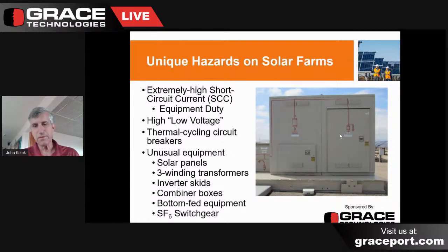And of course, solar farms are usually in a desert, someplace where you have a lot of sunshine, and the ambient temperature might be 120 degrees, and then you operate the system at full load plus a little bit more. You can imagine that it's extremely hot in there, and then it cools down at night. So this thermal cycling really puts a premium on maintenance, breaker maintenance in particular, in the low voltage transformers and low voltage side of transformers. We'll talk about that as we go.